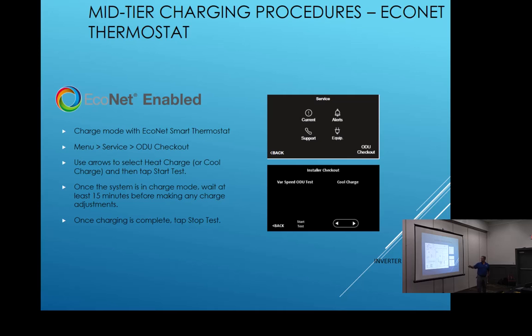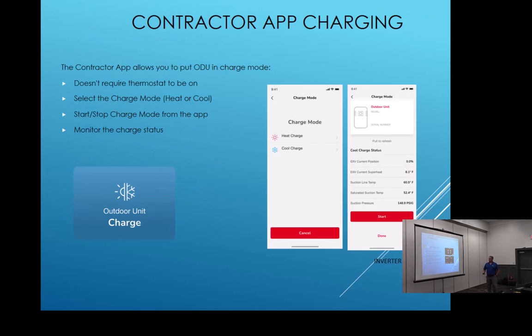Charge mode, we're going to put everything in charge mode when we put our gauges on it, right? That's on the EcoNet. If you don't have an EcoNet, you're going to put it in charge mode through the app, in heat charge or cool charge, okay? You need to have your gauges hooked up to it. Of course you would. How are you going to add refrigerant? But I tell you that because this is misleading. You see the screen that shows you? You can watch your pressures and temperatures. Unfortunately, you can't. They haven't fixed this snafu yet.